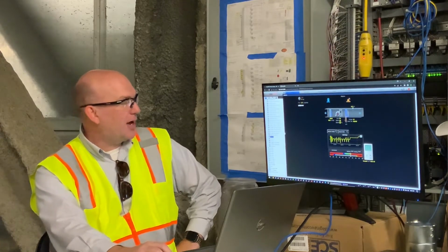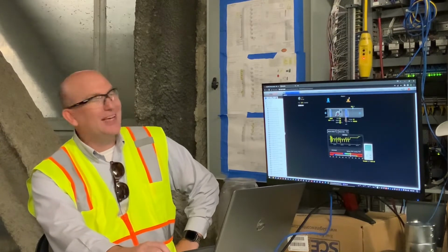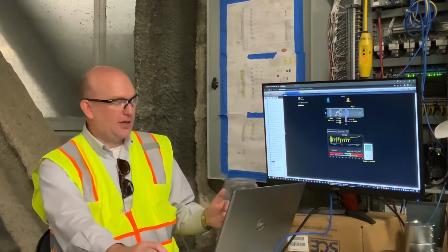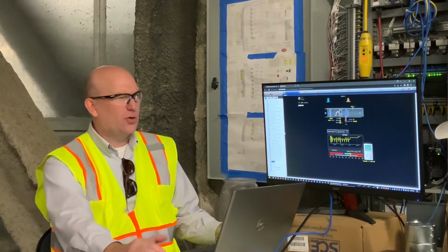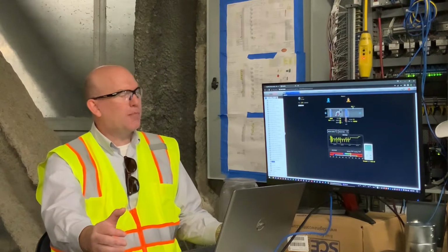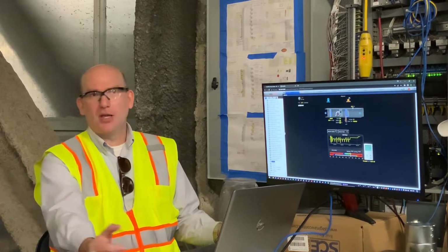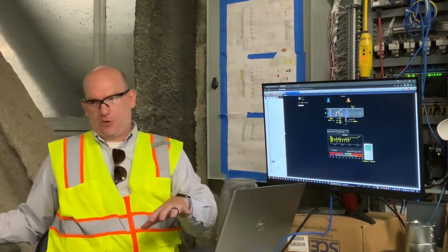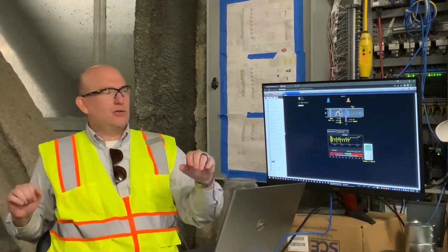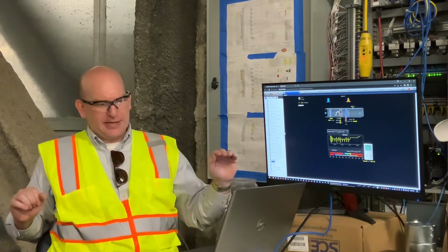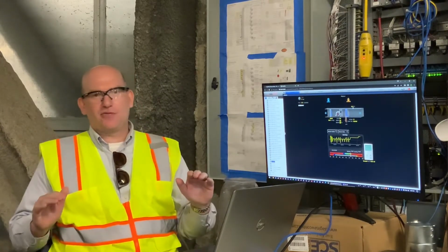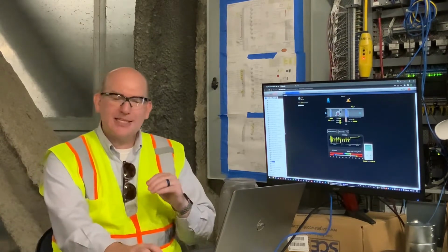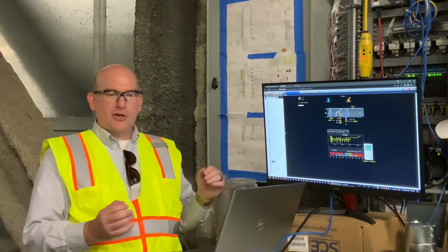There are some unique aspects to each floor. So one of the things that's happening is, up from the ground floor to 6, we're monitoring the fire smoke dampers in the column. There are two separate columns of air that come from the air handlers that are delivered to the floor. Okay, and on ground floor through 6, we simply monitor the state of those fire smoke dampers because it's constant volume. There's no modulation. Once we get to the 7th floor, there's no terminal units.